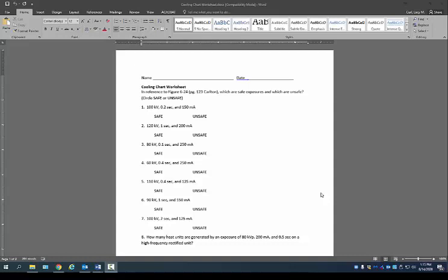In this video, I'm going to explain how to do the cooling charts in the tube safety charts, as well as how to calculate heat units. So the first thing let's look at is the tube rating chart, and this is where we discussed in the presentation you have to determine if an exposure was safe or if it was unsafe.